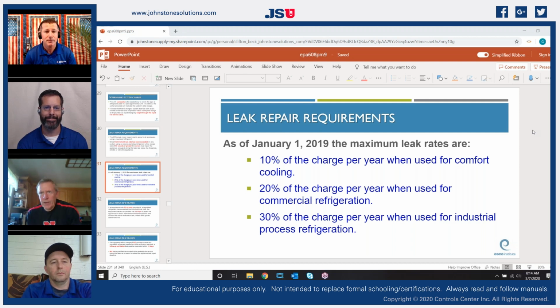I think I'd like to piggyback on that because I know that that's also the importance of keeping accurate records. Yeah. We probably, as a rule, as a service company, didn't do leak repairs if we went out and put a pound or less in a unit and it was the first time we'd ever been on that unit because we don't know what the past was on it. But by keeping accurate records, we could establish the leak rate size even before the government determined we had to fix them because we were trying to figure out.